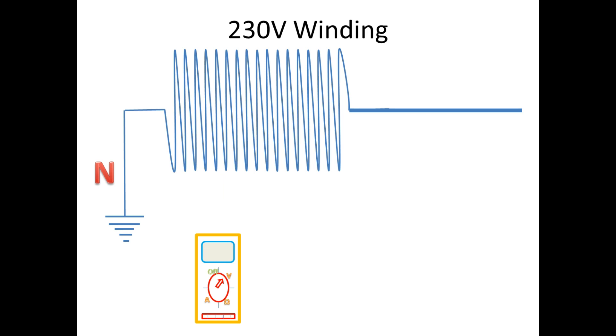Again, I am going to measure voltage from neutral point very near to the neutral point, then we can see the voltage is approximately zero. From this, we come to one conclusion: if we see the voltage from phase side to the neutral point, it will start to reduce or drop toward the neutral point. It will be nearly zero when you reach near the neutral point.